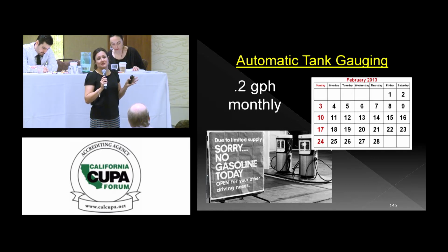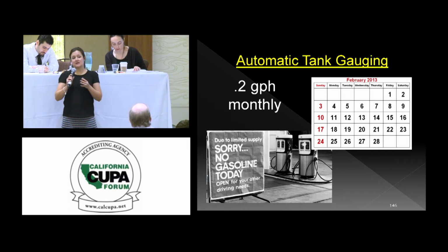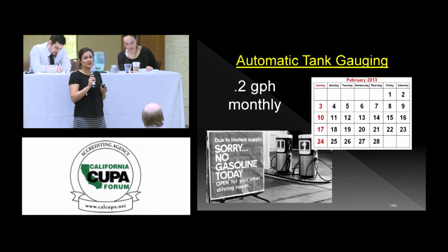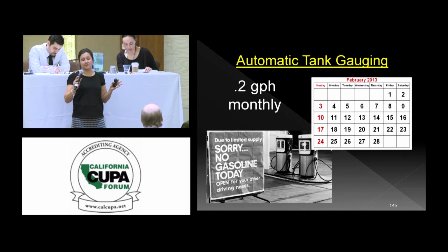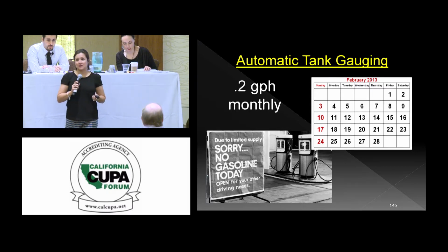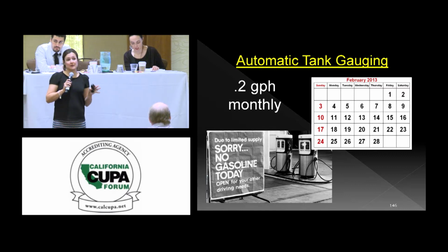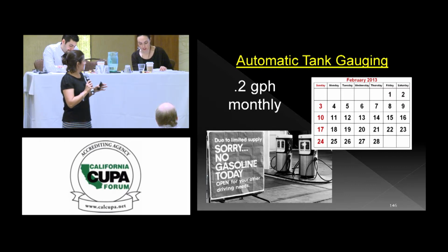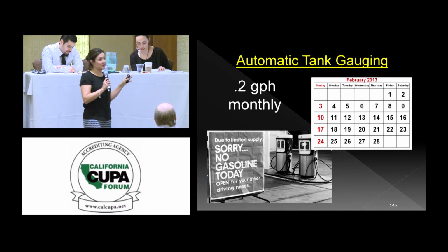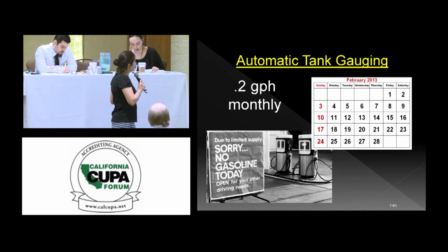So this is a standalone test. You need to pick a time of the month where you are going to run this test. You have to make sure the environment is right for this. You have to have a certain amount of fuel in the tank. You have to have waited a certain amount of time post-delivery. And you have to shut down the station when you run this test. So it can be a little bit of an inconvenience.